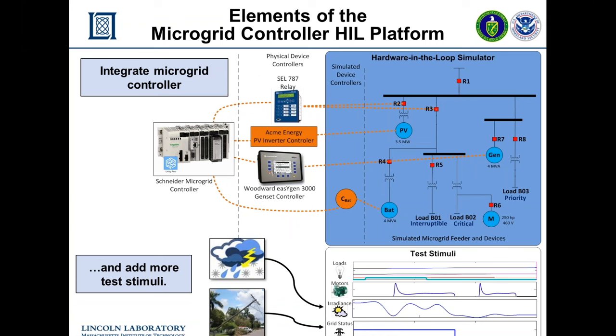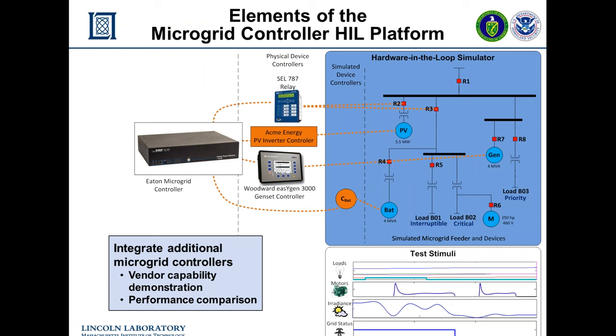The platform elements include irradiance barriers to change PV array power output, a grid outage in the middle of the simulation, and integration with both a Schneider microgrid controller and an Eaton microgrid controller. Both were run through a test sequence to evaluate their behavior. We're looking to integrate with additional commercial microgrid controllers, and we've gotten positive feedback from Schneider, Eaton, and their competitors about the potential value of this platform for demonstrating new project ideas and risk reduction testing.